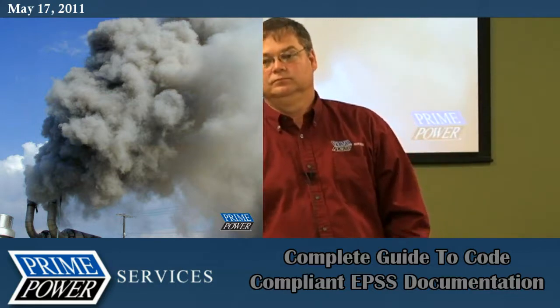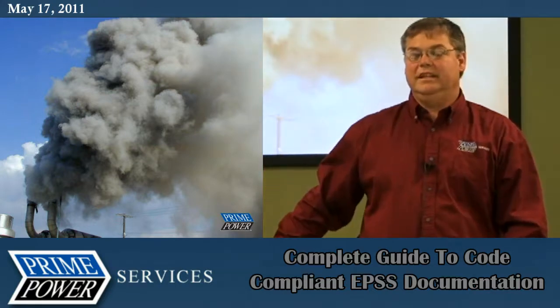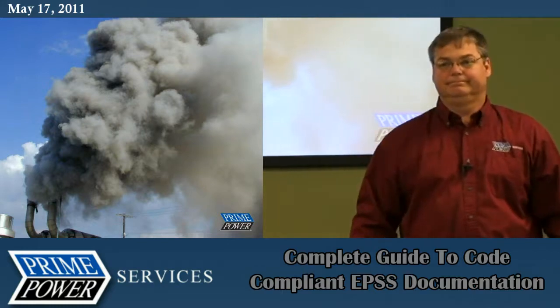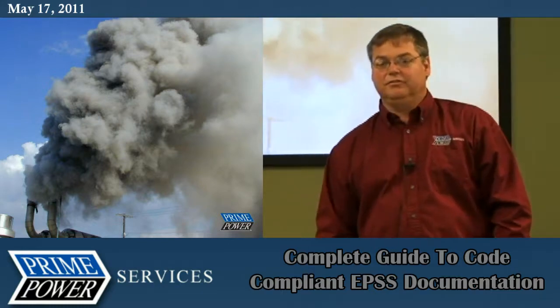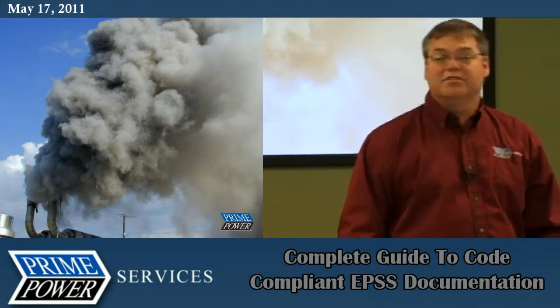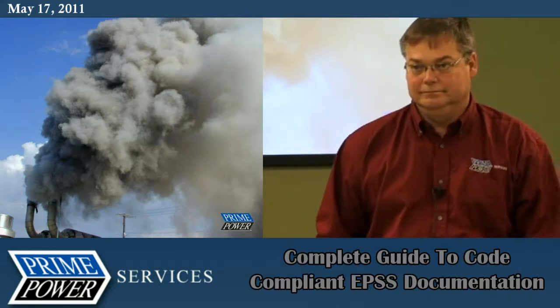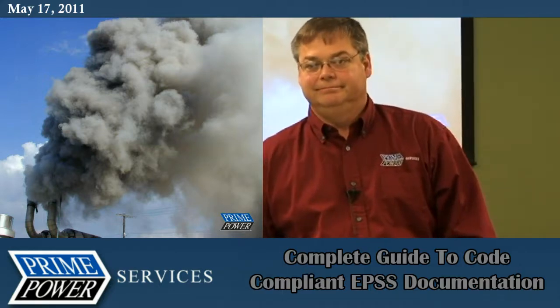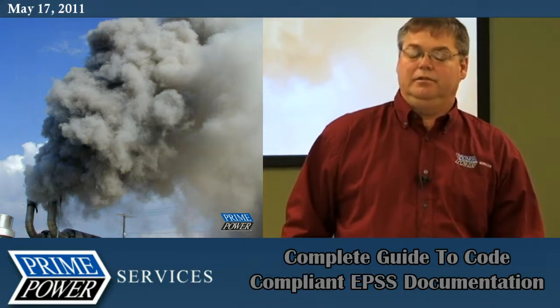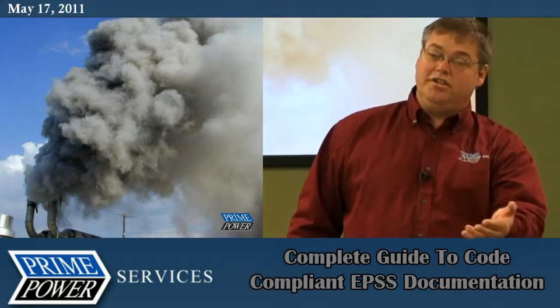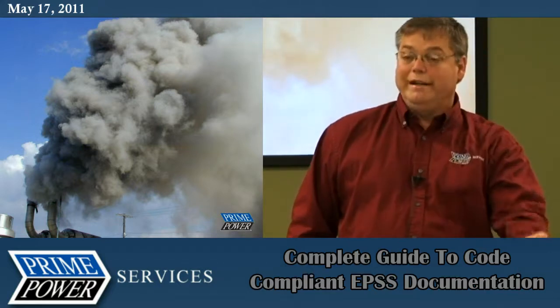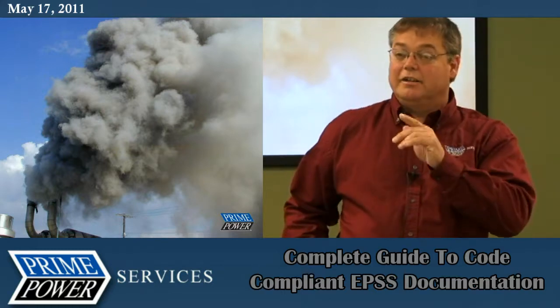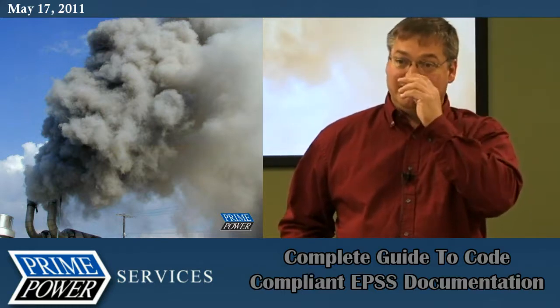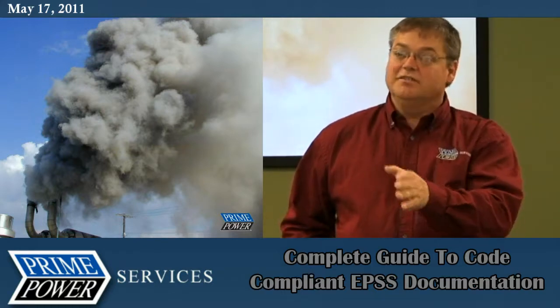Now, we also talk of diesel fire pumps as well as the electrical ones. The diesel fire pumps, the requirement for them is 30 minutes weekly. Yeah, for your diesel engine, for your generator, there is no requirement for a weekly run. It's a manufacturer guideline, a manufacturer recommendation, and it's good practice, but it's not a code.